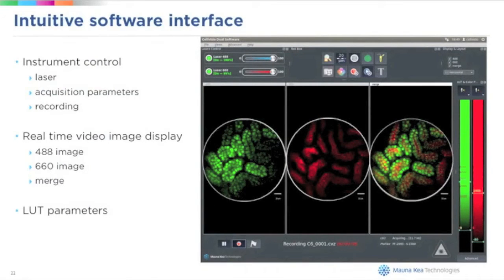So this is the interface of the software. You have the possibility to, of course, control the instrument, so which laser you want to use, at which power, what are the acquisition parameters, and how you want to do recording. It is possible, for example, to perform time-lapse measurements. You also have the real-time video image display of the 488 channel, the 660 channel, and a merge of the two channels. In order to have a good image contrast, you can also play with the parameters from the lookup table.